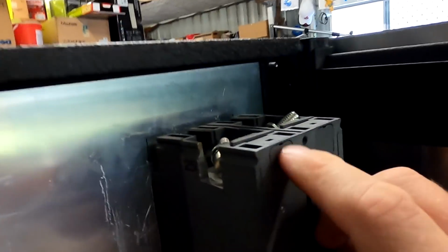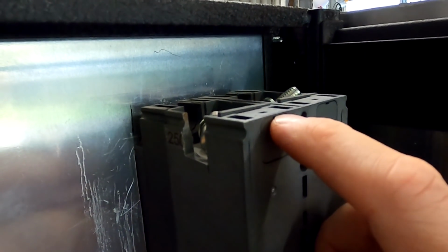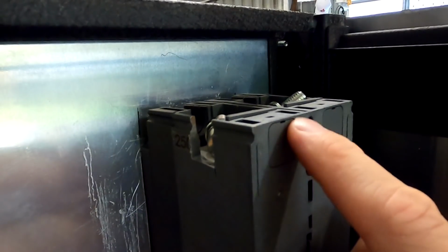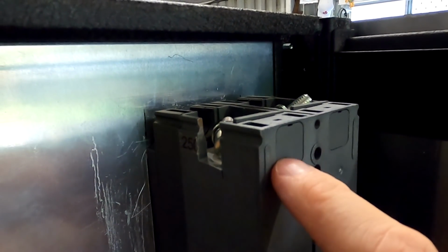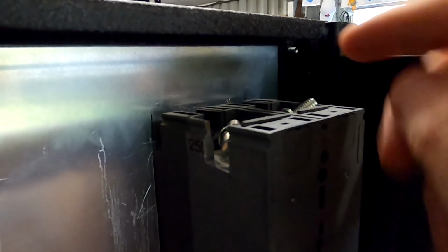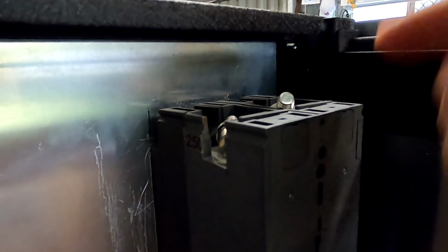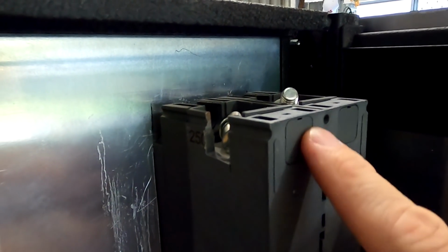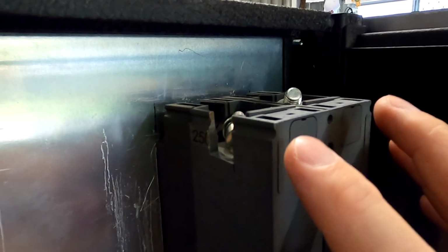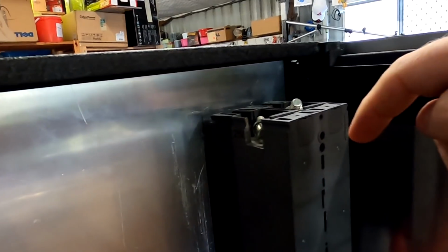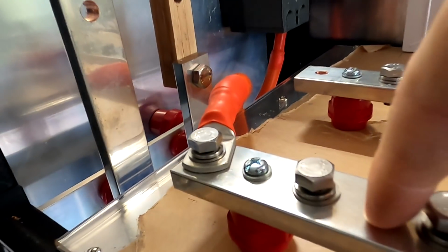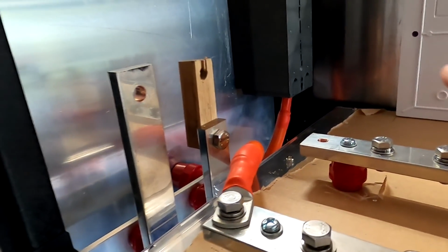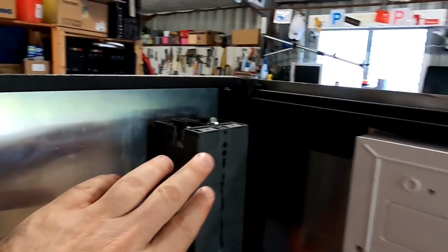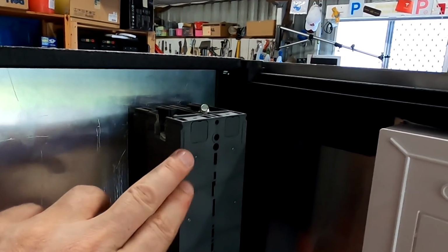And one of you guys has actually suggested here that this one would be a rear mount space for the terminals here. Well, I had this cover open here. You can see the bolt from the underside, but I think this is a location where you mount the circuit breaker directly on top of a bus bar. This is what you use then to screw your terminals down to the bus bar directly without any cabling or something. So unfortunately, it is not a rear mount as such.